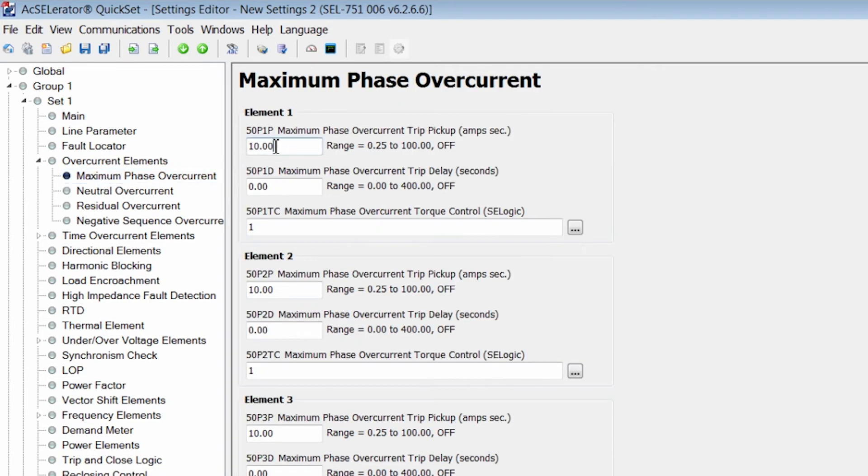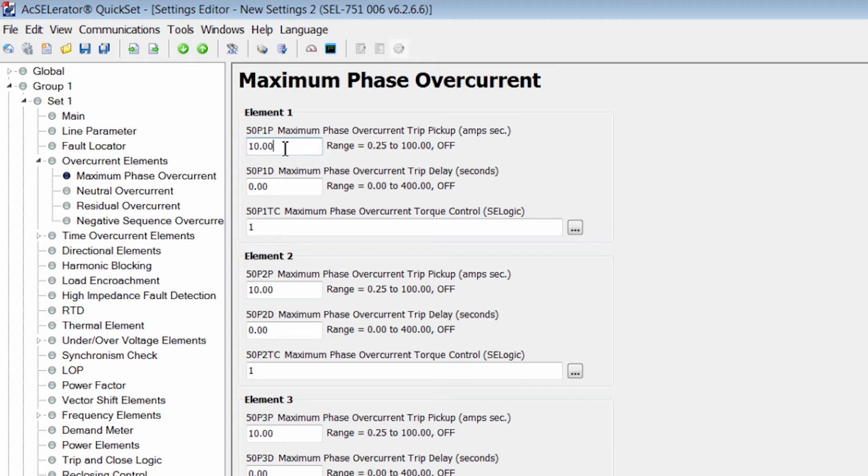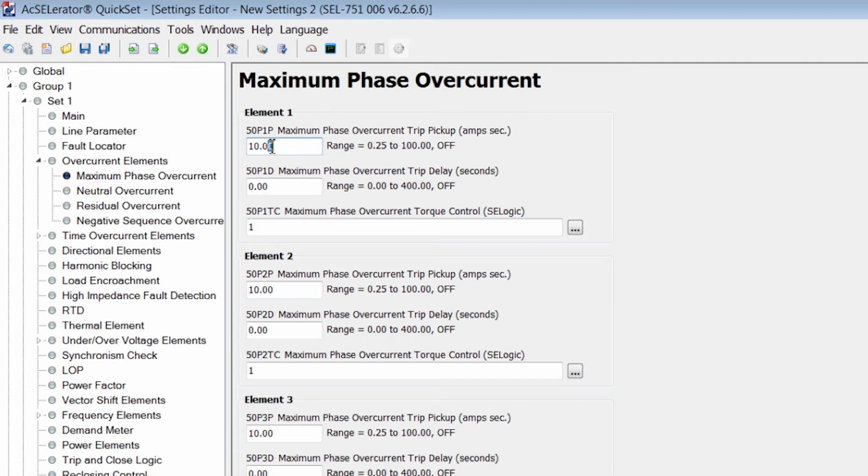So the 50P1P is the setting threshold of the phase overcurrent trip pickup in secondary amps. So if we know the primary amps current, we need to divide it by the CT ratio in order to get the 50P1P setting. Let's just assume that the 50P1P secondary current that we're experiencing for a fault is 15 amps.